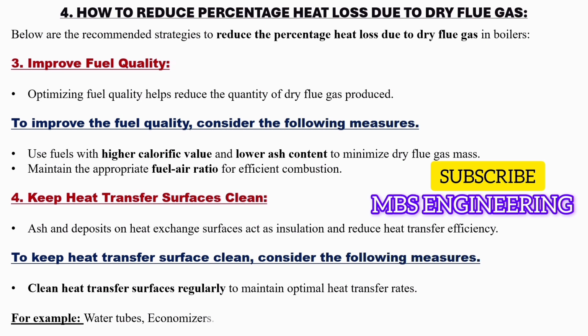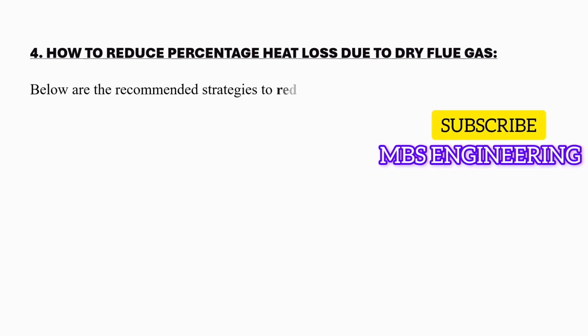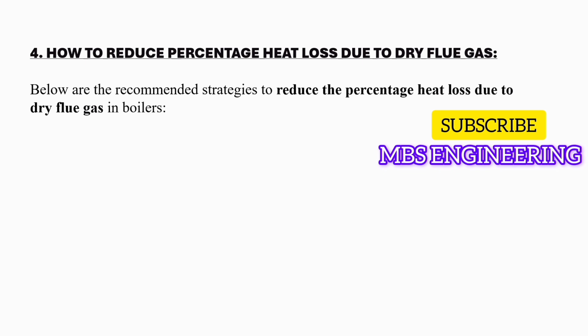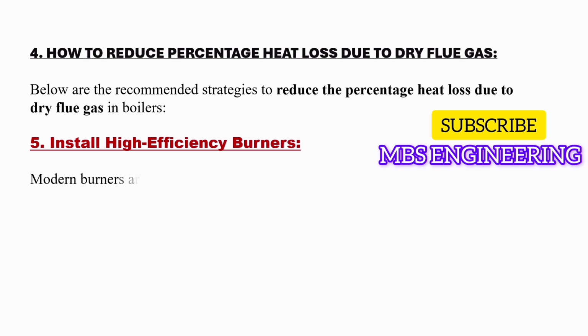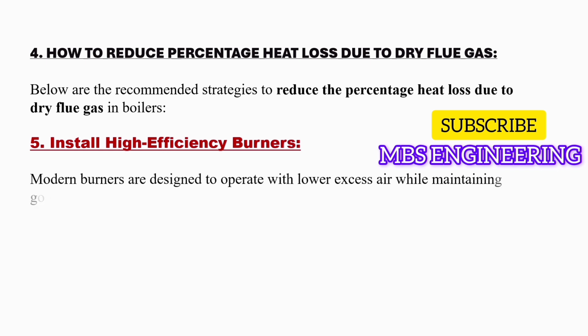Next, we will learn and understand how to reduce percentage heat loss due to dry flue gas in a boiler. Below are the recommended strategies to reduce the percentage heat loss due to dry flue gas in boilers. The fifth recommendation is install high-efficiency burners. Modern burners are designed to operate with lower excess air, while maintaining good combustion efficiency.